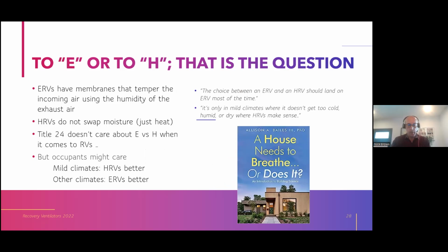Now, a slide on E versus H was warranted. We're all analytically minded, and we often ask the question soon after learning about recovery ventilators, well, do I need an HRV or do I need an ERV? The difference is ERVs have the membranes that, when we cross the airstreams, do the energy saving part, but they also allow moisture to transfer between the streams. So the humidity of the exhaust air influences the humidity of the incoming air. That's the key difference. Whereas HRVs don't swap moisture, ERVs do.